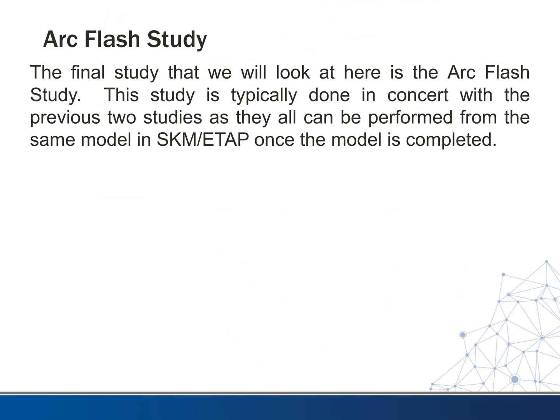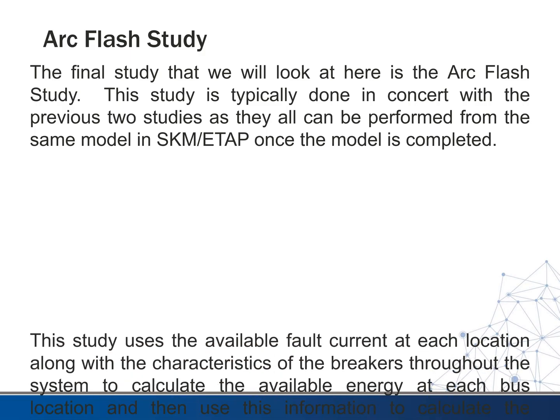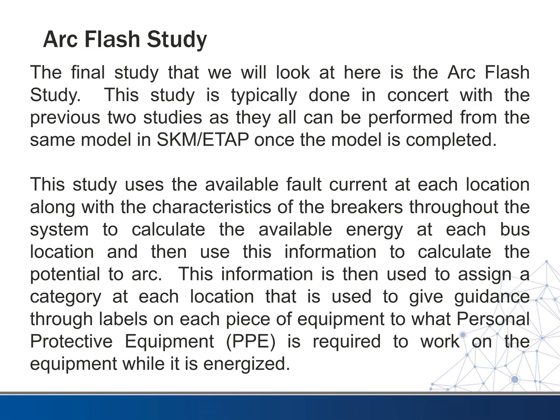The third study and final one we'll look at is the arc flash study. This study is typically done in concert with the previous two studies, as they can all be performed from the same model in SKM and ETAP. You'll usually see this group of studies done at one time — it's easy to do once we get a model built. This study uses the available fault current at each location along with the characteristics of the breakers to calculate the available energy at each bus location.